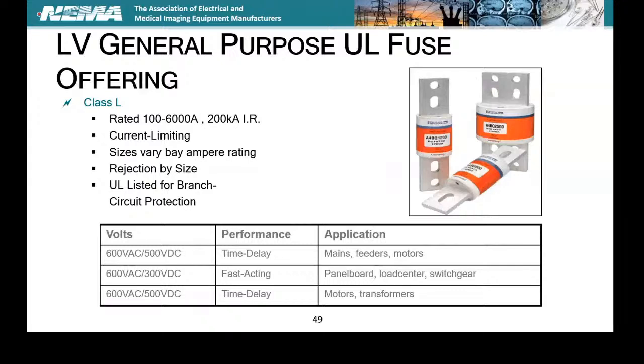Your Class L's are for large fuses. These are the big boys. These go up to 6,000 amps. So you remember 240.67, any fuse 1,200 amps and above may require an arc reduction technology, and it's because when you get to those larger fuses, that fuse curve is adding more and more delay. But you'll see these at the mains because these are the big boys, right? Pretty much. I mean, it goes down to 100 amps as well. But I would say if I was at 100 amp, I might be using a Class J instead of a Class L, depending upon what my goals and objectives were for the system.